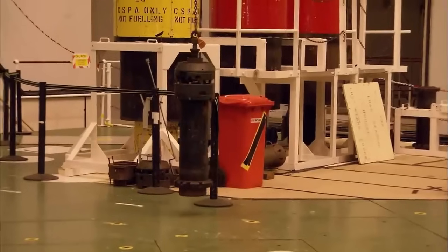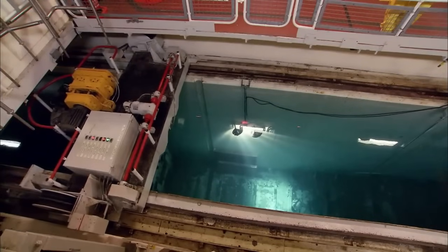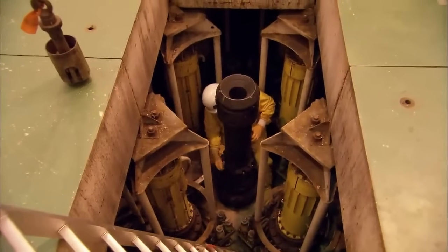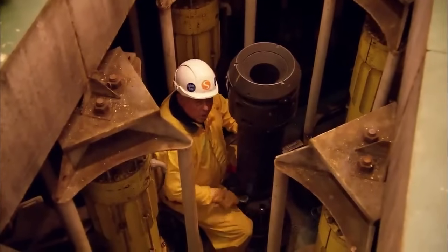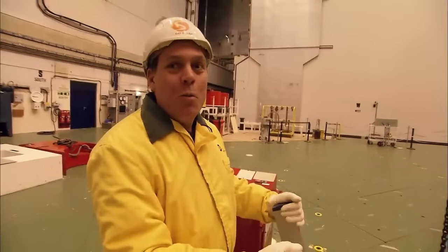Of course, they're not literally going to go in and pull out the fuel. The fuel is handled by the charge machine — a robot crane that pulls out the rod and drops it down a chute into the storage pond. The storage pond's job is to cool fuel rods and shield operators from radiation. In the tsunami-hit Fukushima reactors in Japan, the big fear was ponds boiling dry and fuel rods catching fire, melting or exploding. It was about ten years ago when I first came down here and it was a bit unnerving at first. There's very little dose down here now. Before 2006 when the reactor was running, if you had to go up to the top of the charge machine, you're in the 40s — that's how warm it was.